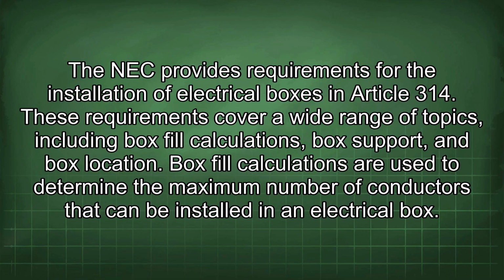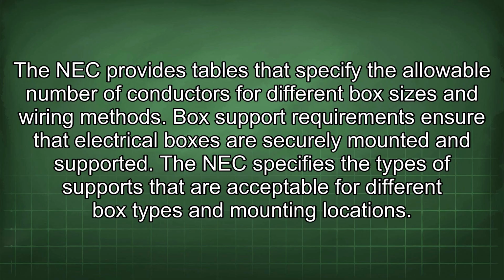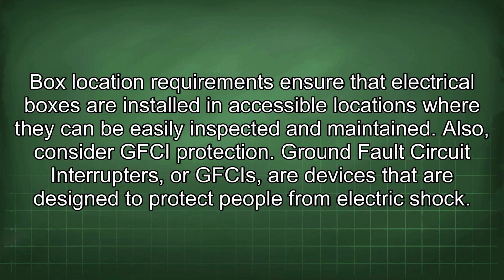Box fill calculations are used to determine the maximum number of conductors that can be installed in an electrical box. The NEC provides tables that specify the allowable number of conductors for different box sizes and wiring methods. Box support requirements ensure that electrical boxes are securely mounted and supported. The NEC specifies the types of supports that are acceptable for different box types and mounting locations. Box location requirements ensure that electrical boxes are installed in accessible locations where they can be easily inspected and maintained.